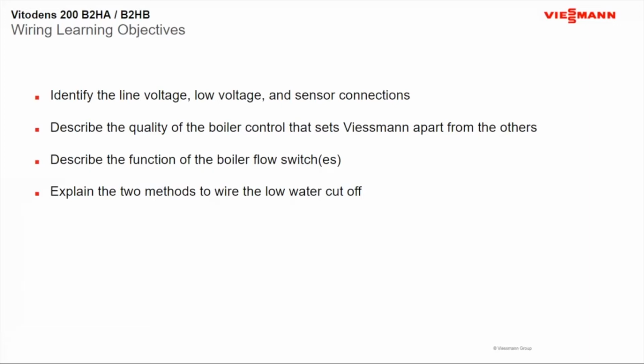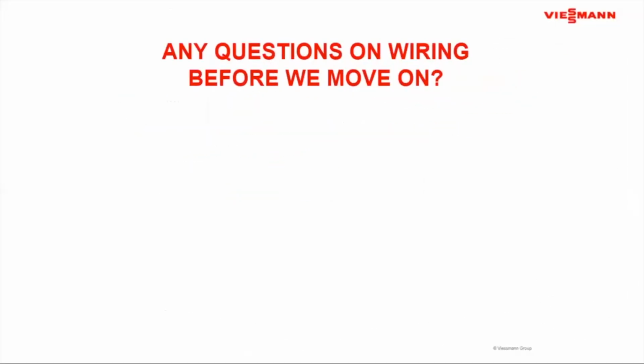If it's off, I would just replace it. To go through all that trouble and get into the back of the boiler and get to those flow sensors in the back just to clean them, I would think it would be better to replace them. And if you're going to do that, a little helpful hint is I would take the burner out and get that stuff out of your way. It's only 6 bolts. It comes off pretty easy. And you can see that through our maintenance of the boilers itself.